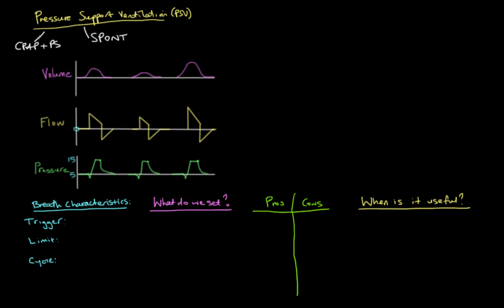We support the patient by giving them pressure. Looking at these waveforms — at the bottom we have a pressure waveform. The baseline along the white line is 5, because our baseline pressure is usually elevated — we set a PEEP level. The patient decides that they want a breath and makes an effort to breathe. That causes a drop in the pressure in the circuit — a small deflection below 5 — which tells the ventilator that the patient is trying to take a breath.